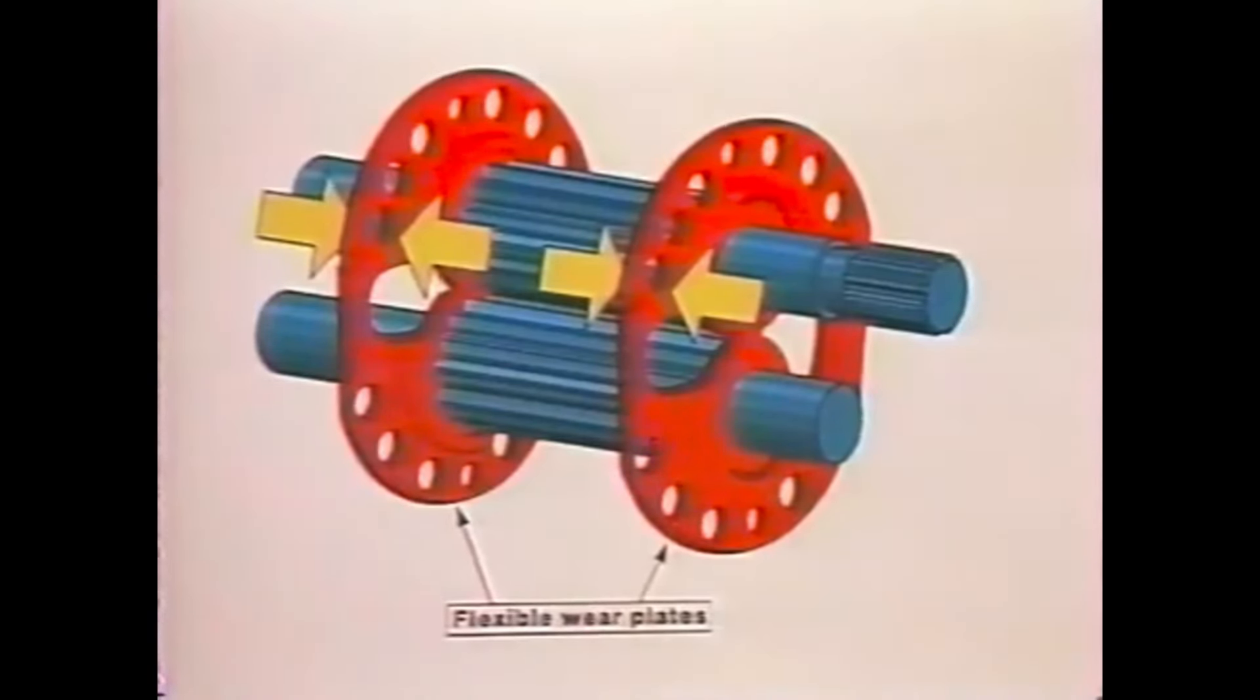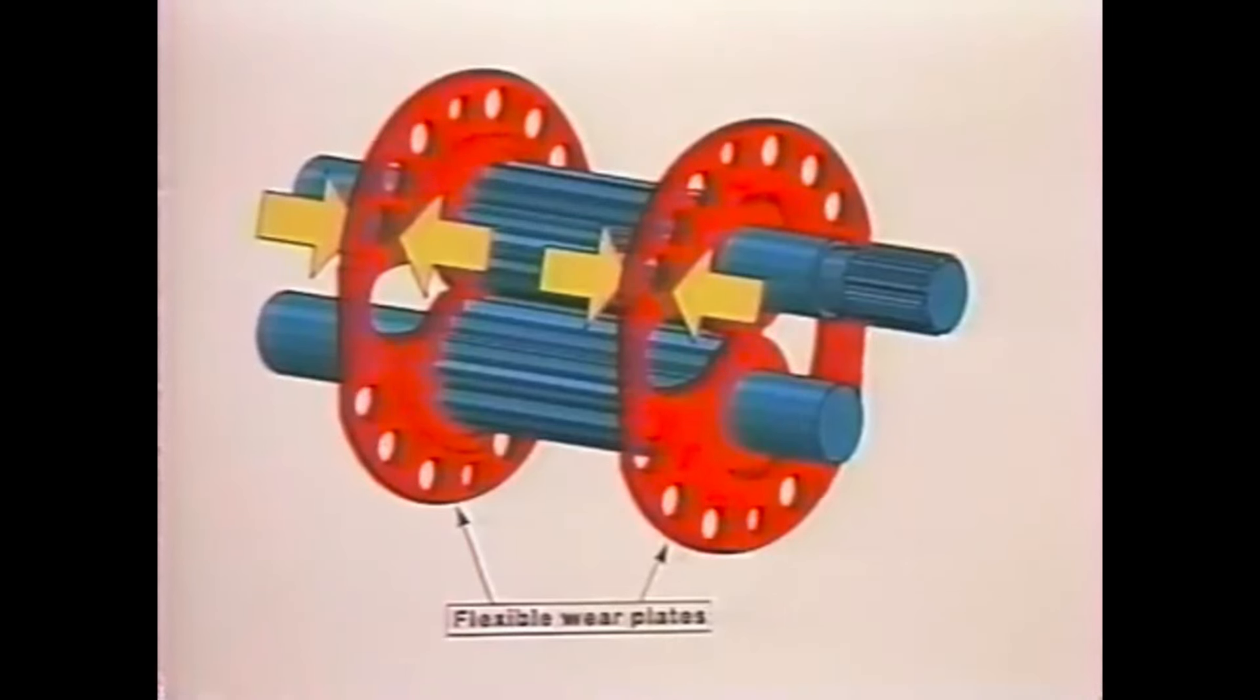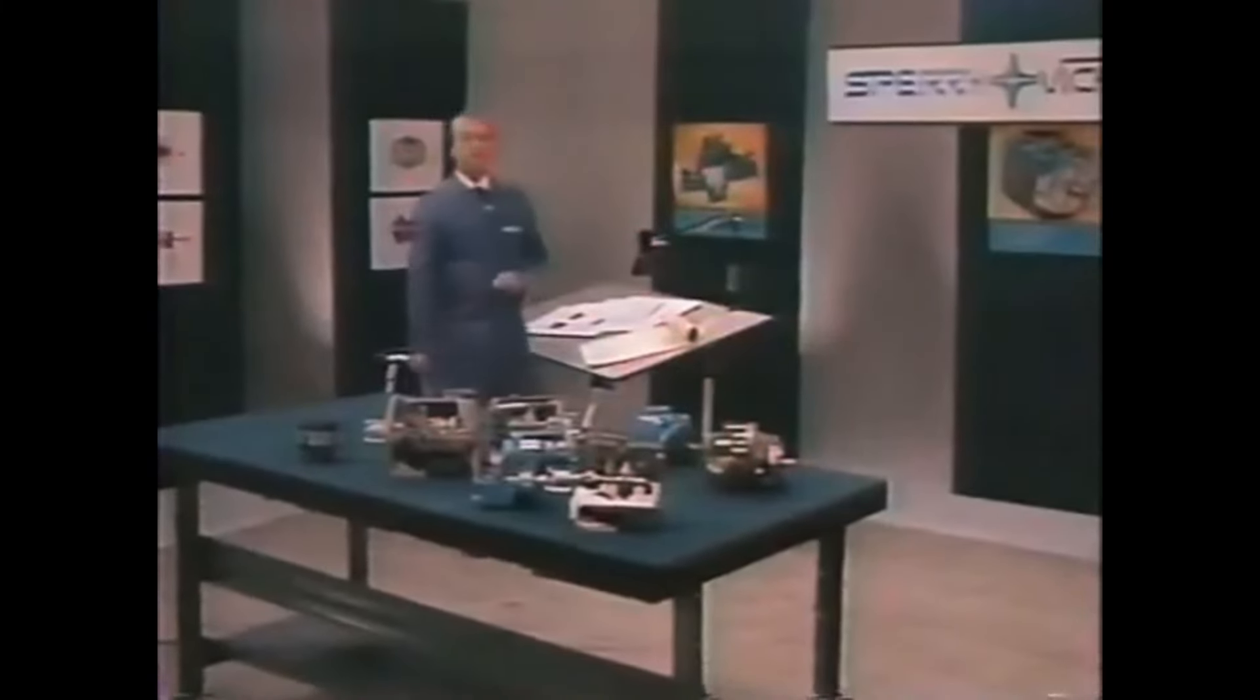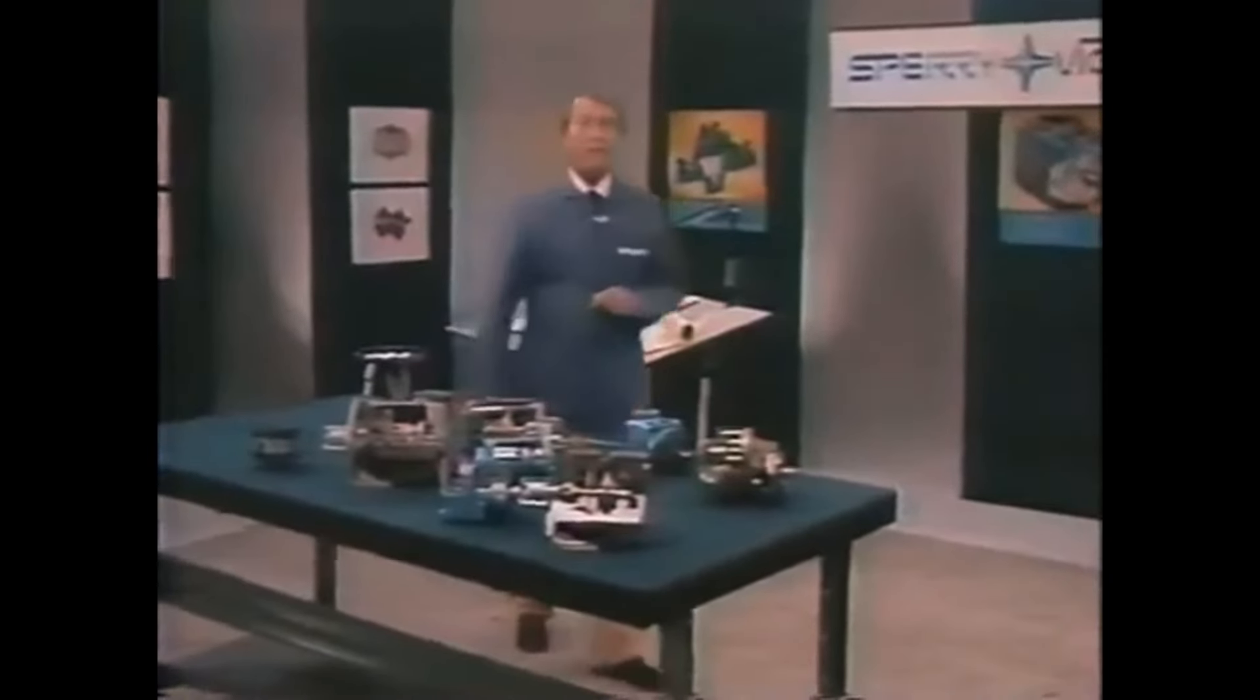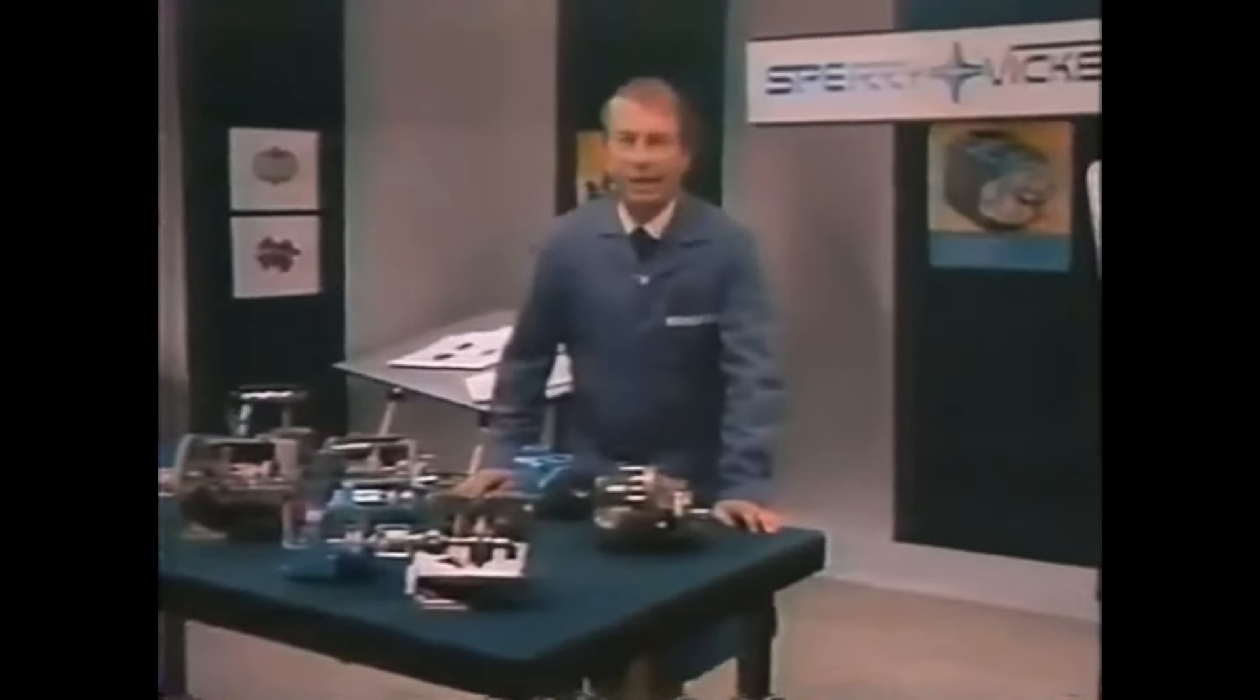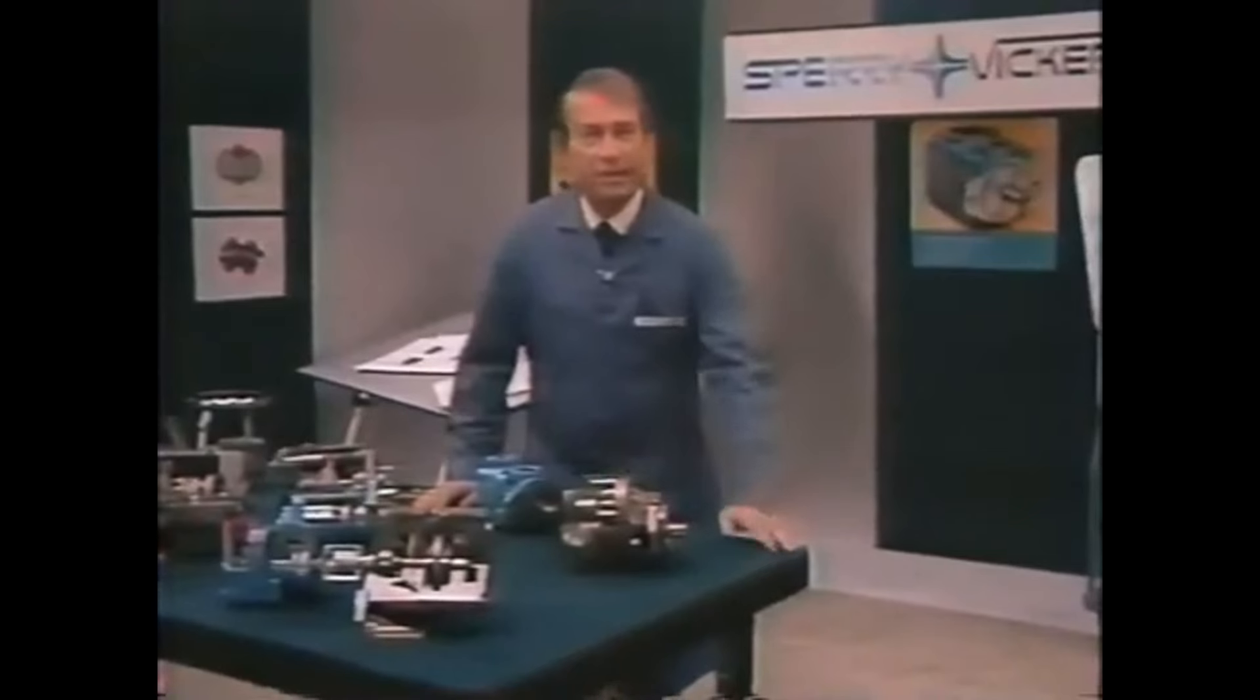This performance is at least partially the result of the addition of bronze-faced flexible wear plates. These plates are pressure loaded against the side faces of the gears, reducing clearance to a minimum. Passages in the wear plates also permit oil under pressure to extend farther around each gear to reduce the unbalanced hydraulic loading inherent in this type of pump. Sperry Vickers gear pumps range in size from 7 to 50 gallons per minute at 1,200 RPM, although considerably higher drive speeds are permissible. They're available as both single and double units.